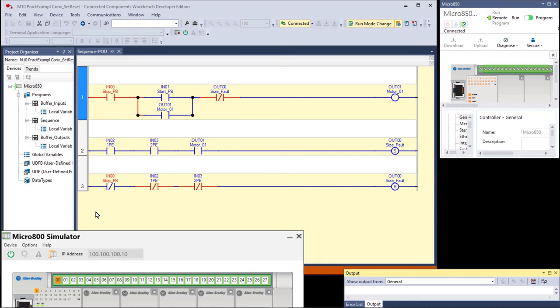At this point, did the conveyor stop running, leaving the longer carton where it was detected? Yes. Is rung number 1 still true? No. Is output 0 on or off? It's off. The motor stopped. Is rung number 2 still true? Well, that depends, but no, because the motor's not running, therefore the rung's going to go false.